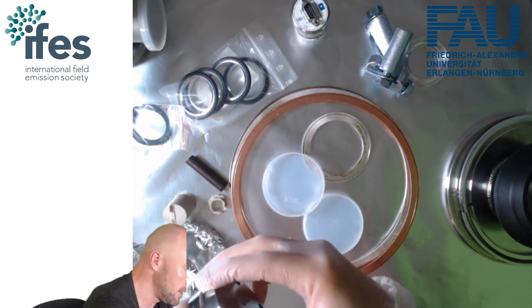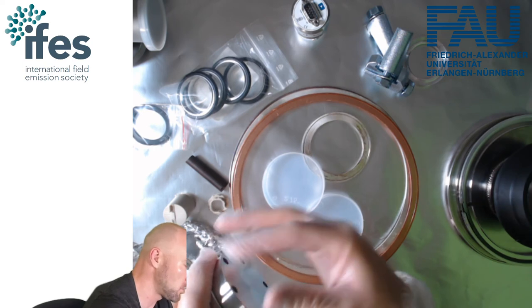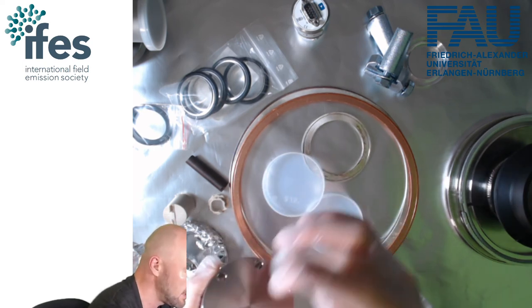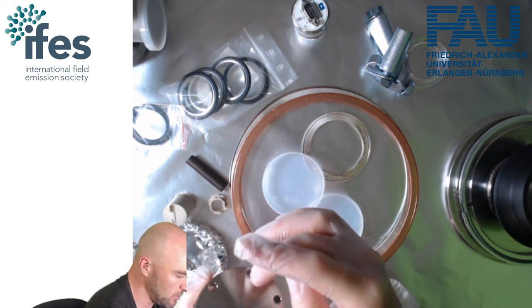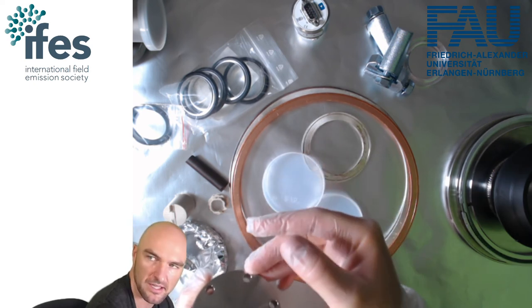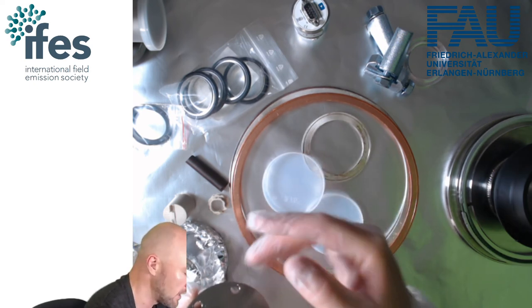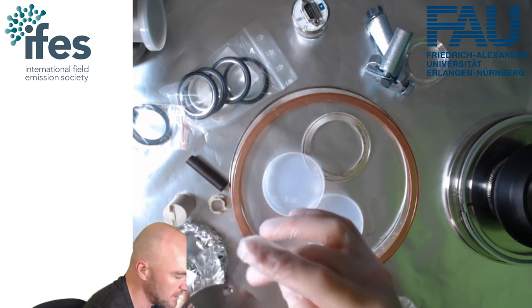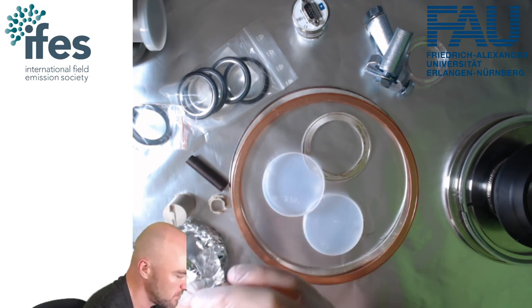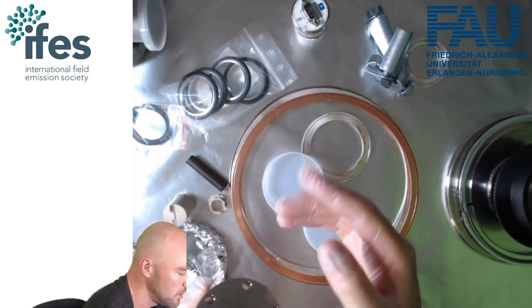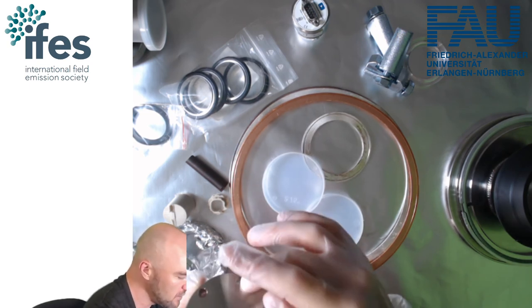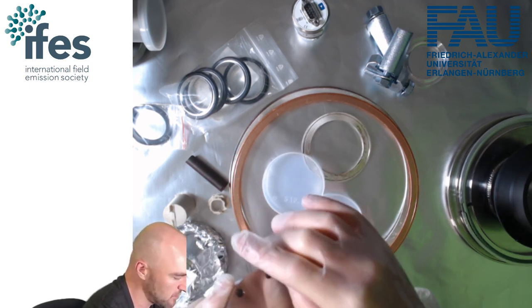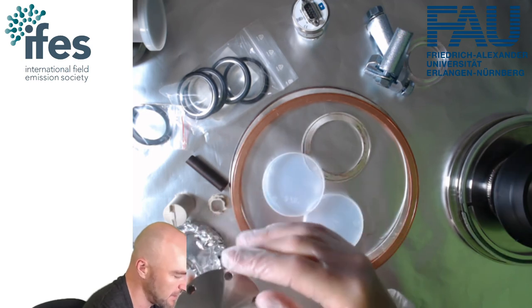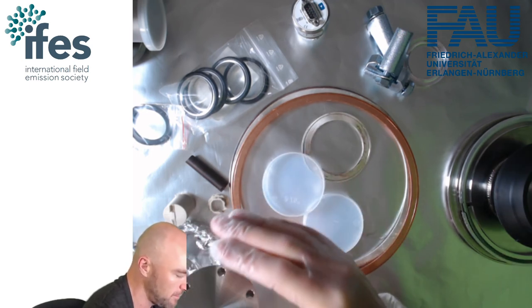And so you need to align them, you need to put the gasket in between, and then you put the bolts in, and then you tighten the bolts just like you would tighten the bolts in your car's wheels. So you always tighten them across, so first this one and this one and this one and this one and this one and this one, in various stages. So I usually tighten them by hand until everything sits flush on the copper gasket.